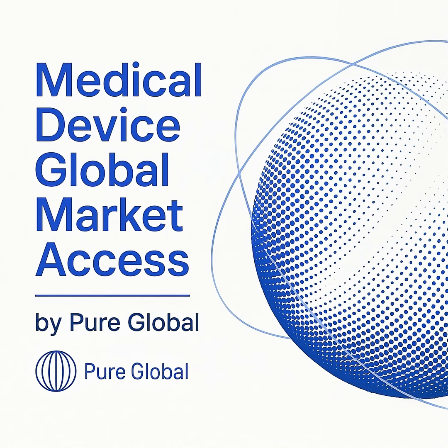In this episode, we delve into a critical component of the U.S. regulatory landscape for medical devices, 21 CFR Part 812, the regulation governing investigational device exemptions, commonly known as an IDE. An IDE is the formal mechanism that allows a medical device that has not yet been cleared or approved for marketing to be shipped lawfully for the purpose of conducting clinical investigations on human subjects.